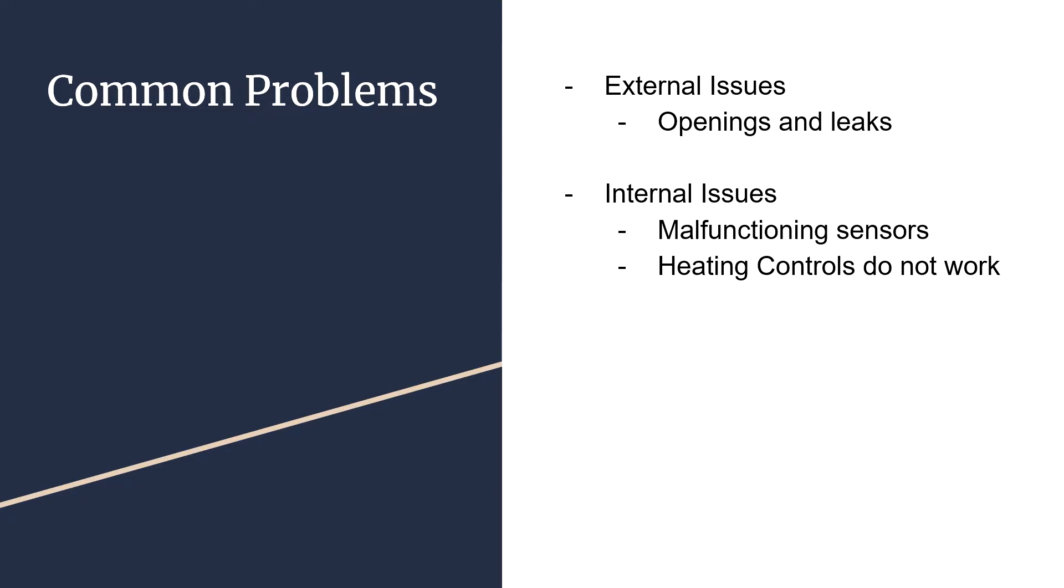There are internal issues on the other hand. One major thing is malfunctioning sensors that don't sense the right temperature. It's very easy to tell. You can set the temperature or humidity to a certain level and use your hand or stick your nose in there. You can probably tell about the humidity. If humidity is 85%, you can feel that it's very wet in there.